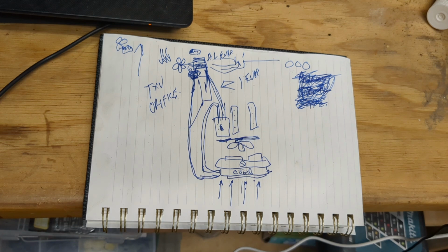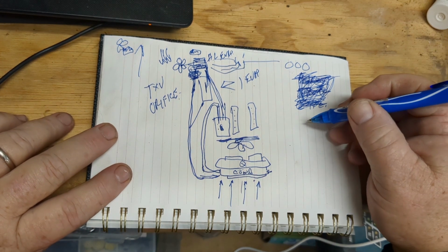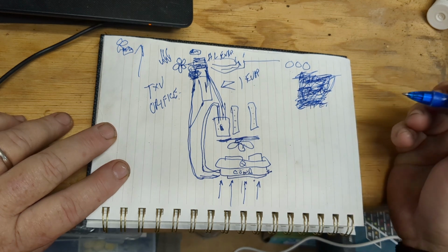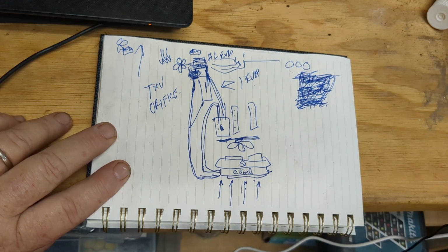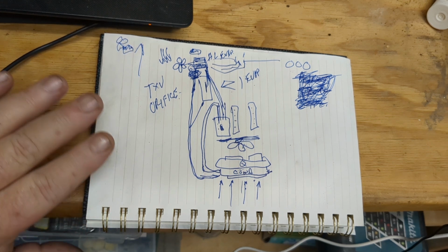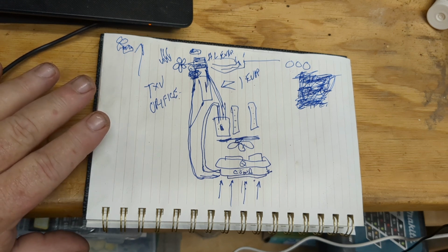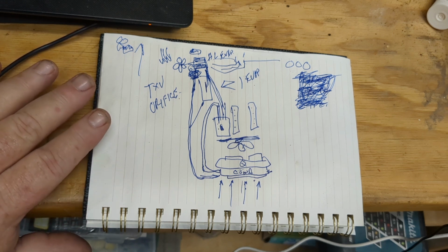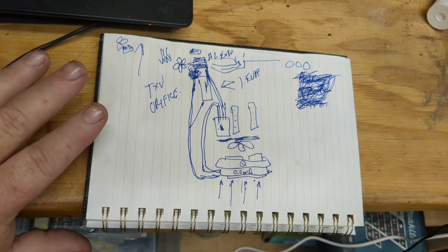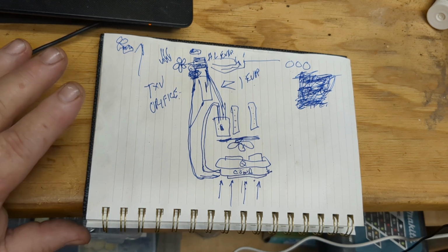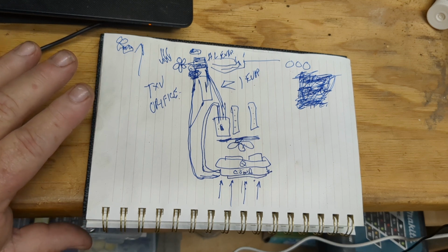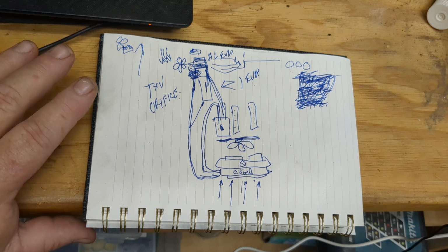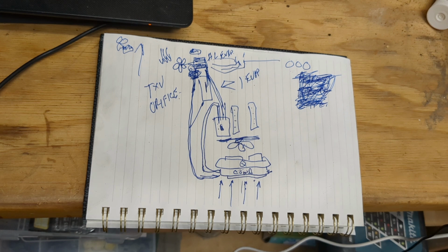Now, here's the important thing. A lot of the professional mechanics will weigh in the refrigerant. They'll say it's supposed to have 23 ounces or whatever. Well, okay, fine. I think that's just a standardized North America generic load of refrigerant that should function halfway decent, just to make it work. But it doesn't always apply in Florida, because we get some unbelievably humid and hot days down here. So that's why I always dial them in and put in what I want, and I do that through pressure. I don't pay any attention to the sticker.